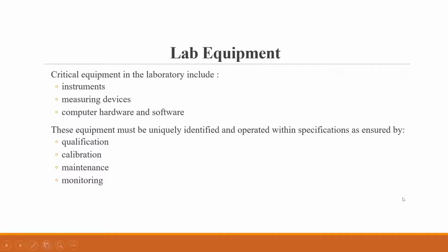If you have a big facility in the blood bank or clinical laboratory, and you have, for example, 5 centrifuges, they must be uniquely identified. As an inspector, I look for the identification. Normally, right in front of the machine itself, there is an identification.